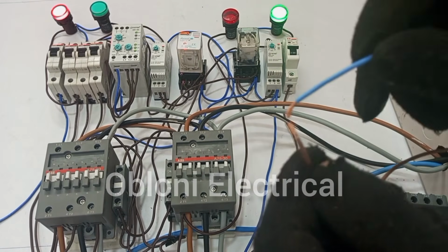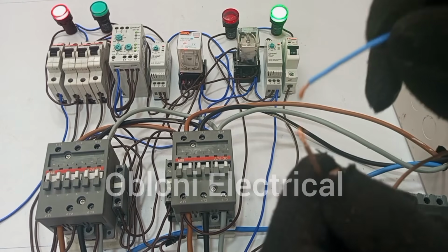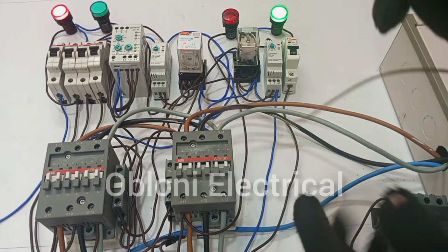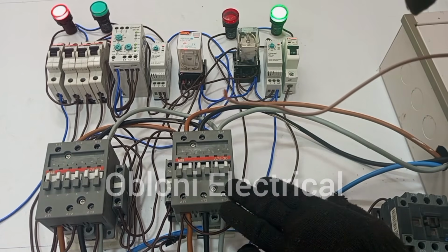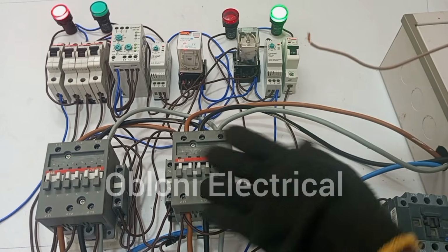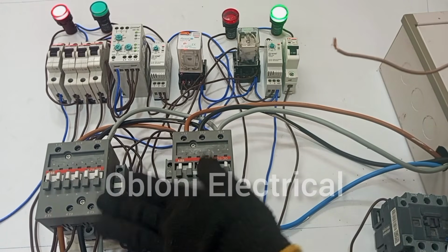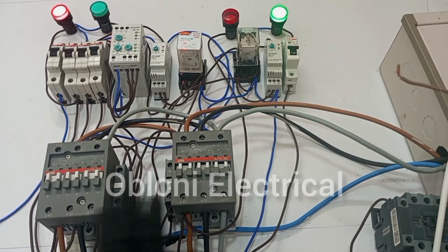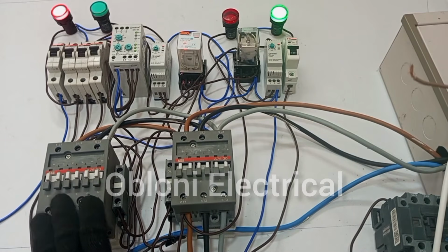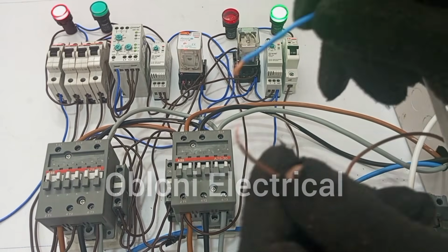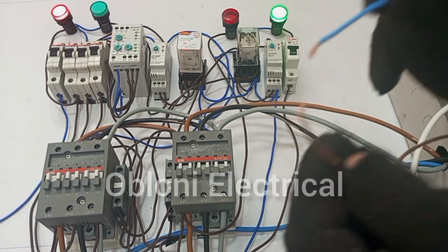So that the moment these contacts close, the generator will start and then transfer power to the load. Right now, the generator is working. As soon as main power is restored, the generator should turn off for the main supply to take over. And that is done by this signal wire that goes to the generator.